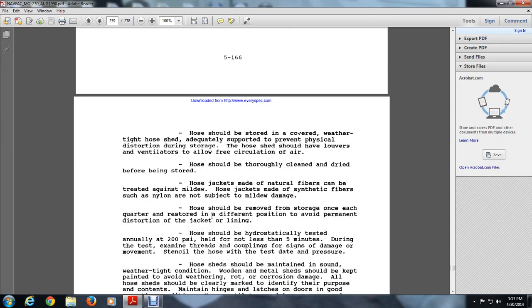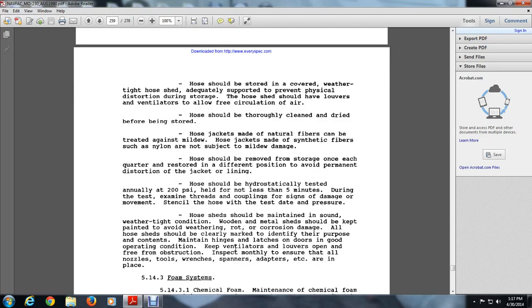Jacket-lined hoses should be hydrostatically tested annually at 200 psi, held for not less than 5 minutes. During the test, examine threads, couplings, and signs of damage, and the stenciled markings of the hose. The hose houses should be maintained in a sound, weathertight condition. Wooden and metal sheds should be kept painted to avoid weathering, rot, and corrosion damage. All houses should be clearly marked to identify their purpose and contents. Maintain the hinges and latches of the doors in good operating condition.